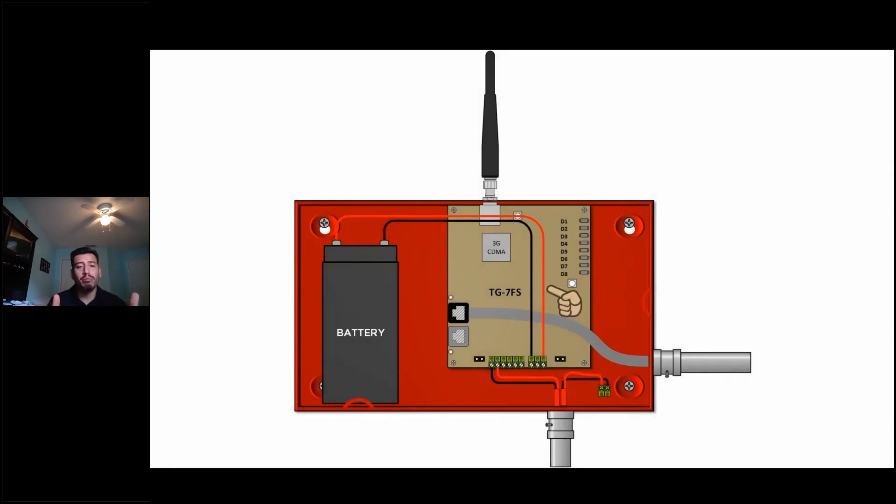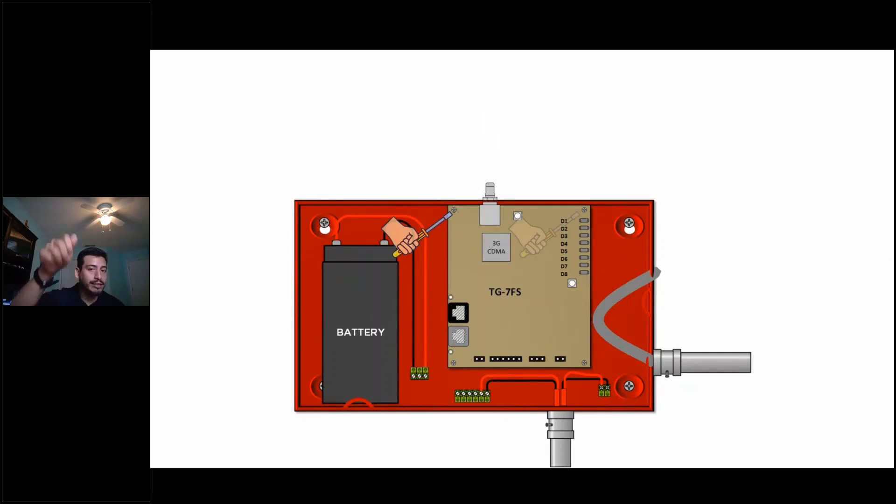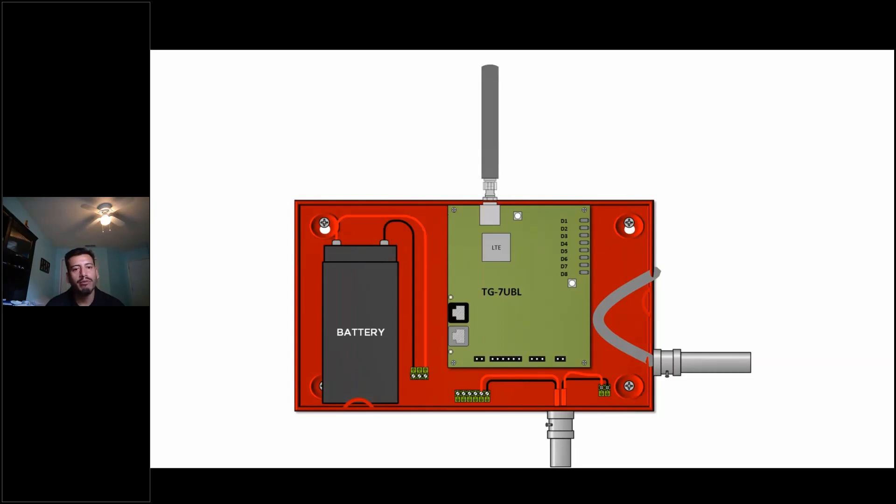You're going to go through your TG7 product, whether it's a burg or a fire system. You're not going to remove the wire — you're just going to pop off the terminal blocks, pop off the connection for the RJ, and remove the antenna. That's a key one. Remove the antenna, pop off the old board, take the new board out of the box, put it back in, and then do the same thing in reverse. Pop the terminal blocks back where they belong and go through the activation.